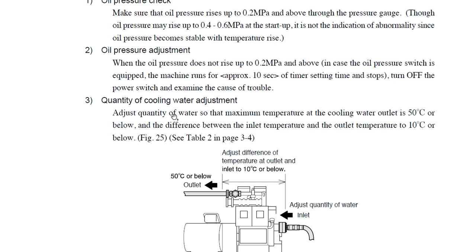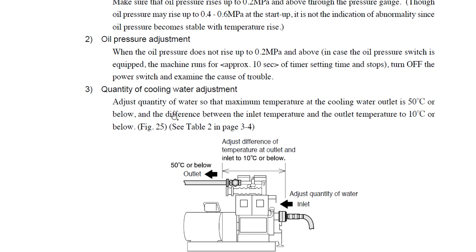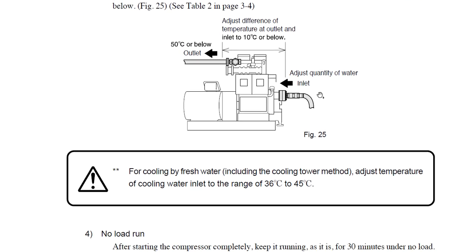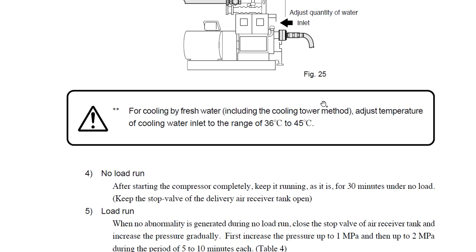Next, we will check that the quantity of cooling water adjustment is proper. Adjust the quantity of water so the maximum temperature at the cooling water outlet is 50 degrees Celsius or below, and the difference between the inlet temperature and the outlet is 10 degrees or below. We have seen the table and spoken about that.